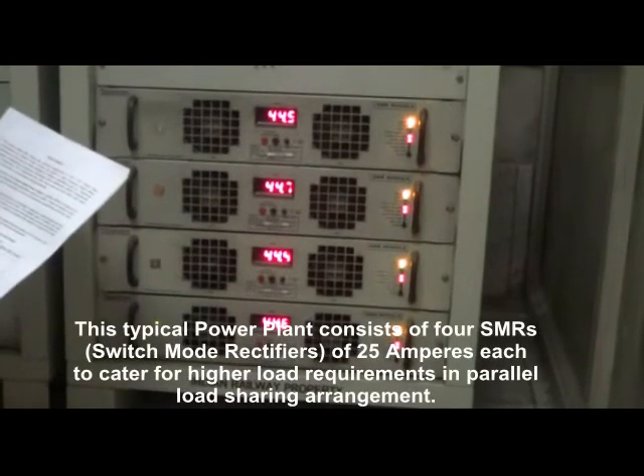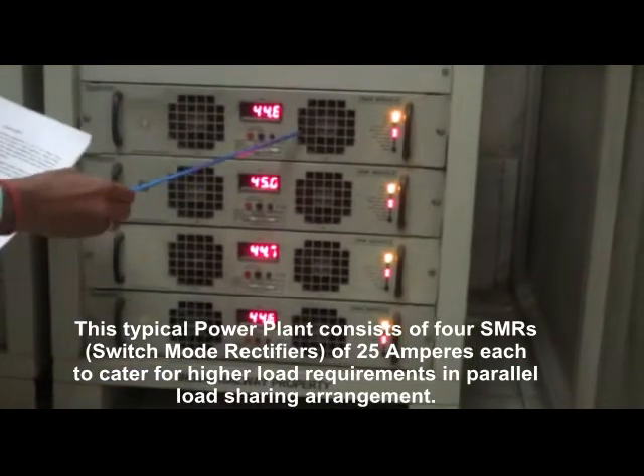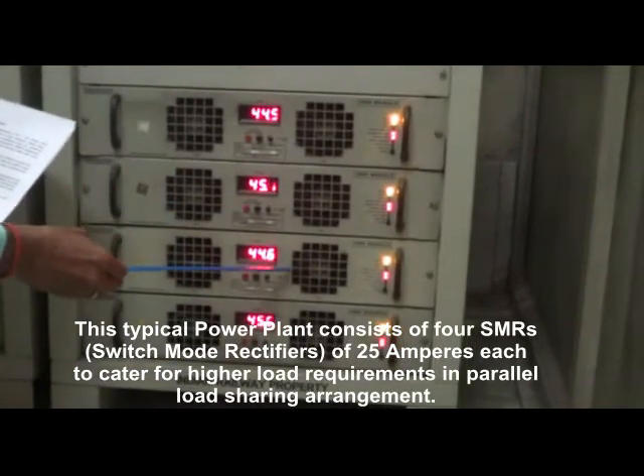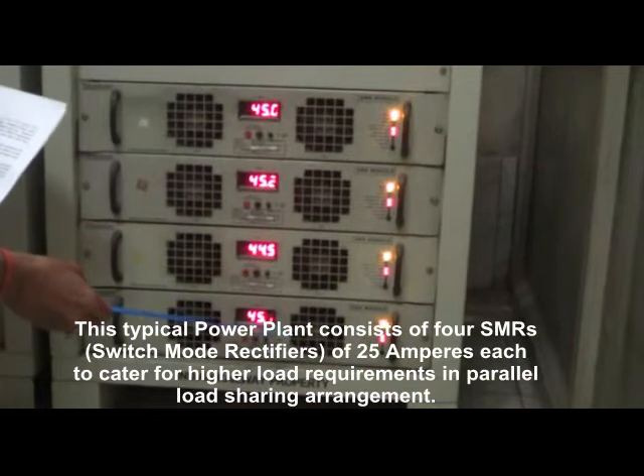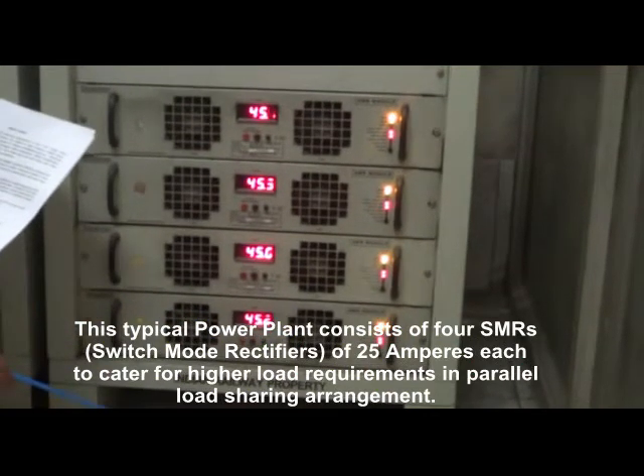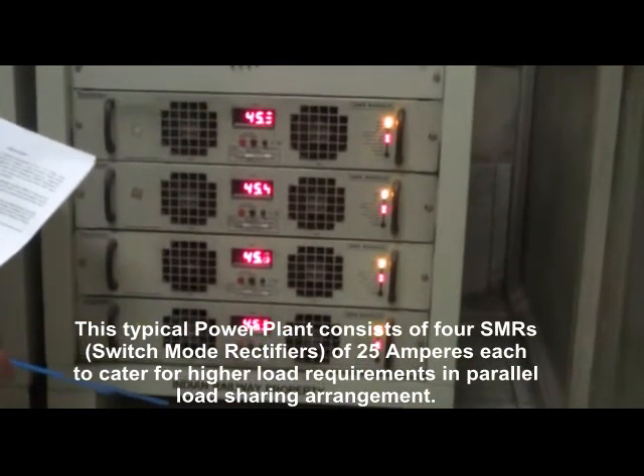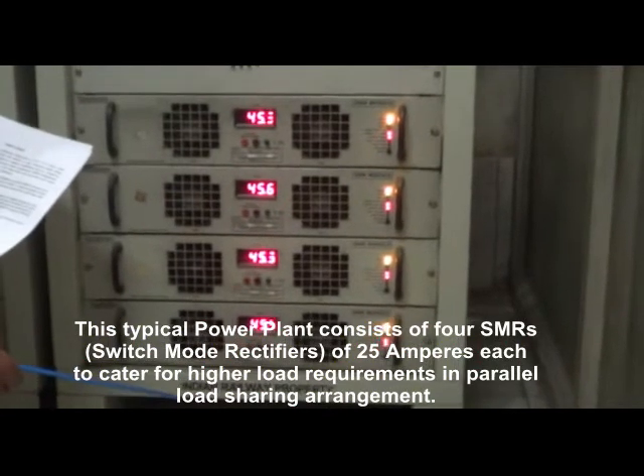This typical power plant consists of 4 SMRs, switch mode rectifiers, of 25 amperes each to cater for higher load requirements in parallel load sharing arrangement.